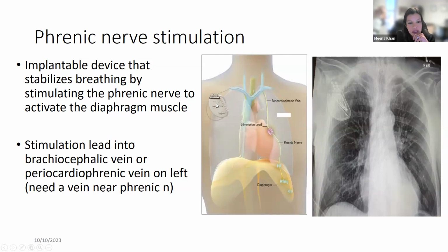This is done by interventional cardiology through a catheterization procedure where they put the device in, and the sense lead, which senses whether or not the patient is breathing, is actually within the generator. And then there's a stimulation lead that's snaked through one of the veins near the phrenic nerve, so either the brachiocephalic vein or the pericardiophrenic vein. You need a vein that is by the phrenic nerve because it stimulates the phrenic nerve through the vein. You do have to have a phrenic nerve that is conducting. So if somebody has a neuropathic condition where their phrenic nerve is not functioning, they cannot get this device. There has to be conduction through the phrenic nerve for this device to work. And it will stimulate the hemidiaphragm, and then when it stimulates the hemidiaphragm, actually both sides will engage for breathing.